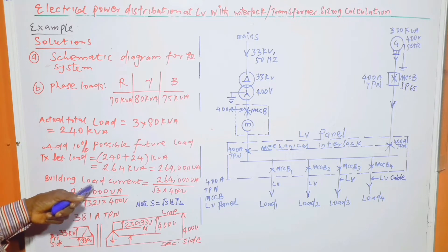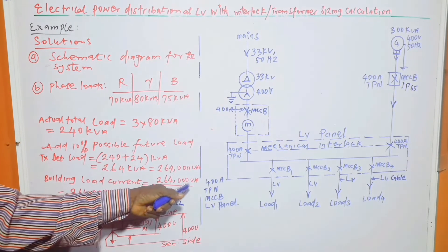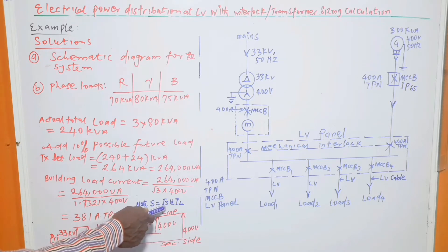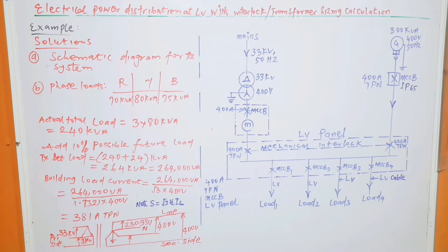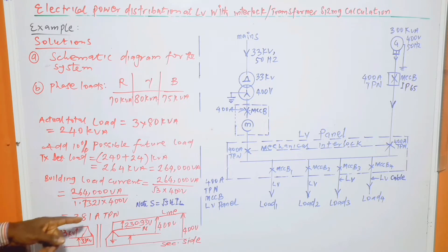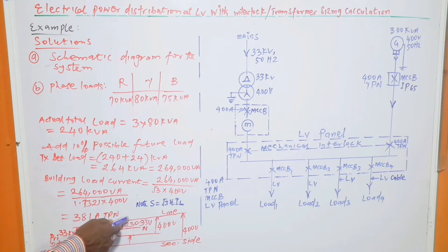Then we can move further to calculate the building load current, which is equal to 264,000 VA divided by root 3 times 400 volts. From this formula S is equal to root 3 times V line times I line, from which we can calculate the I line to be equal to 381 ampere triple phase with neutral. In this case, it doesn't mean that the neutral current is 381, we are just saying that we have 3 phases plus neutral. It is the line current, which is equal to the phase current in this situation, that is 381.